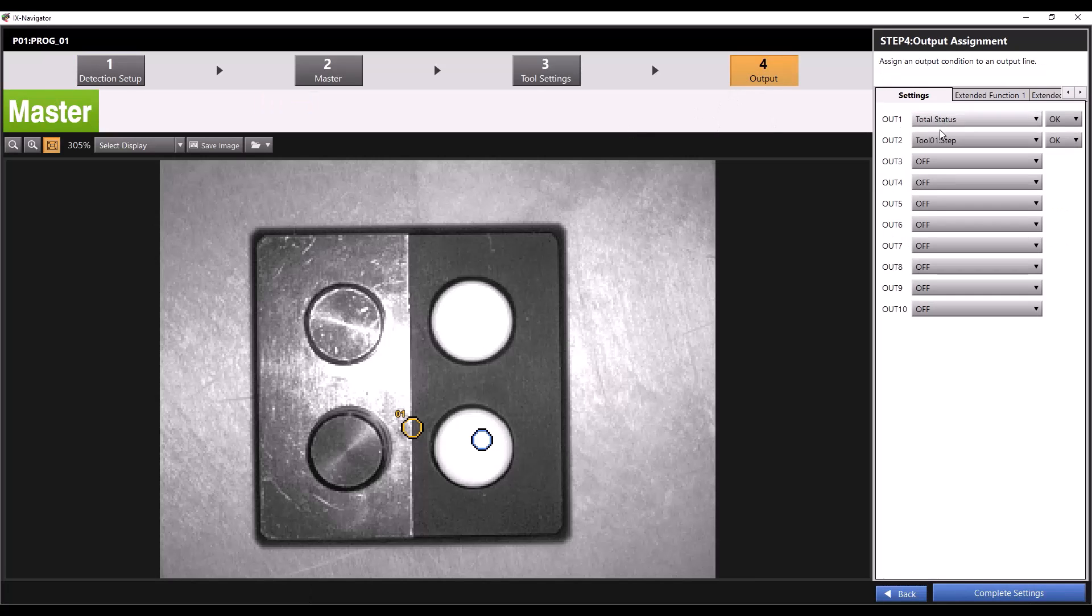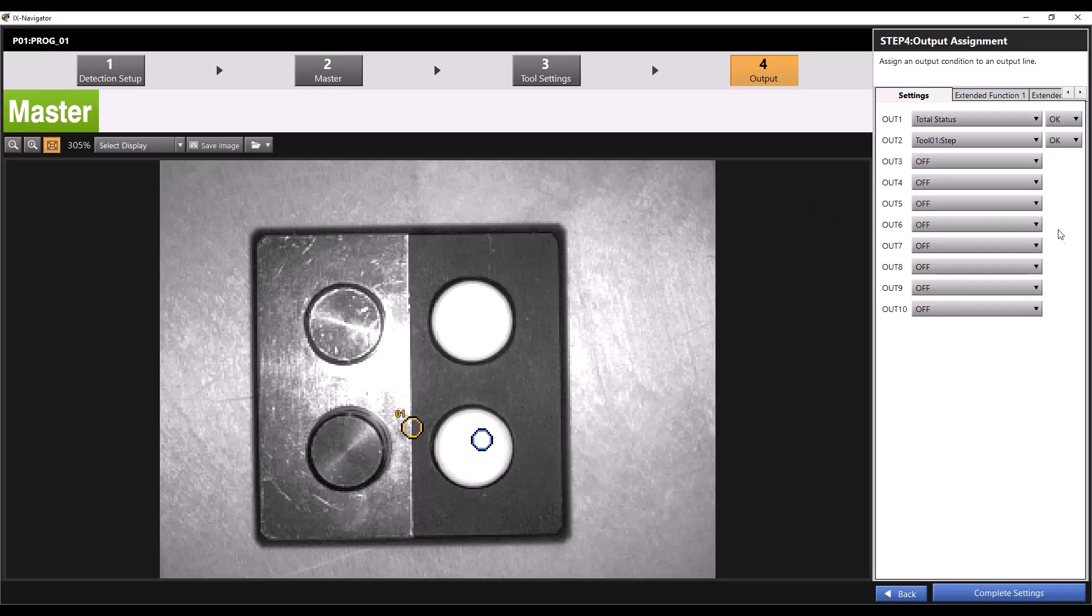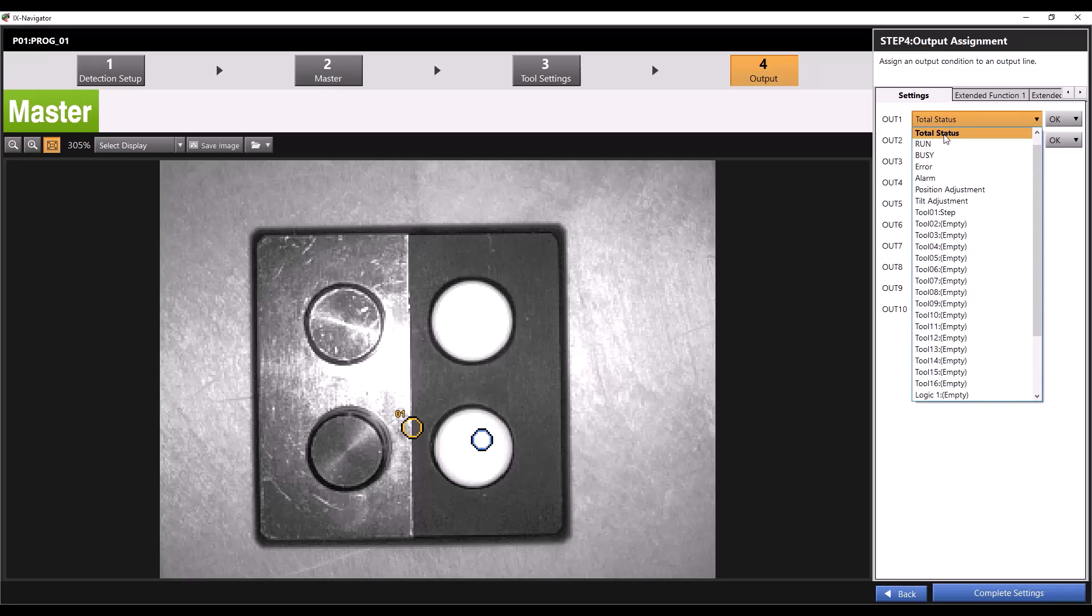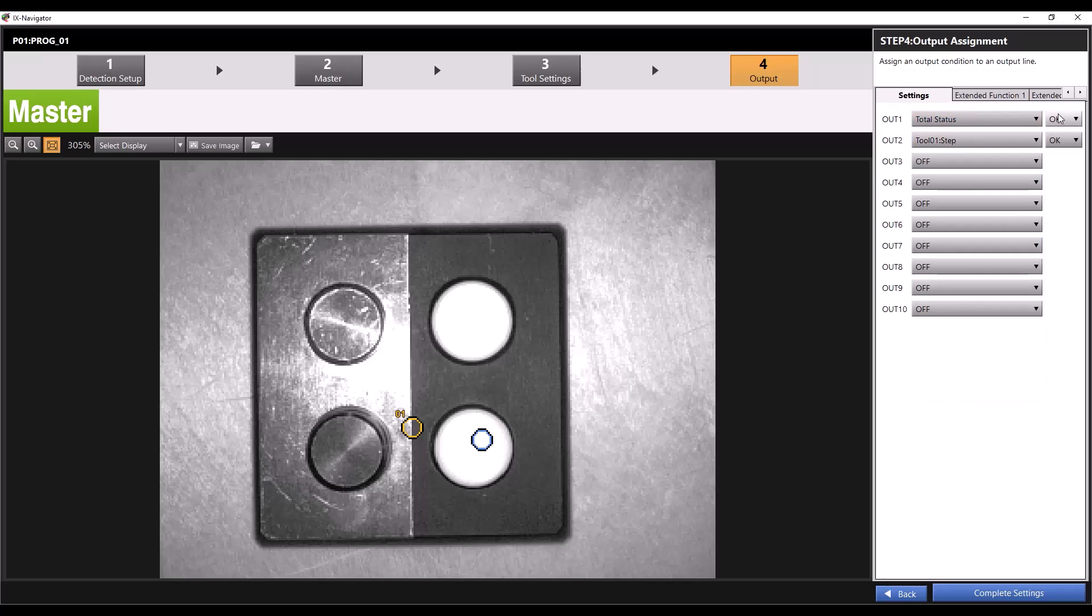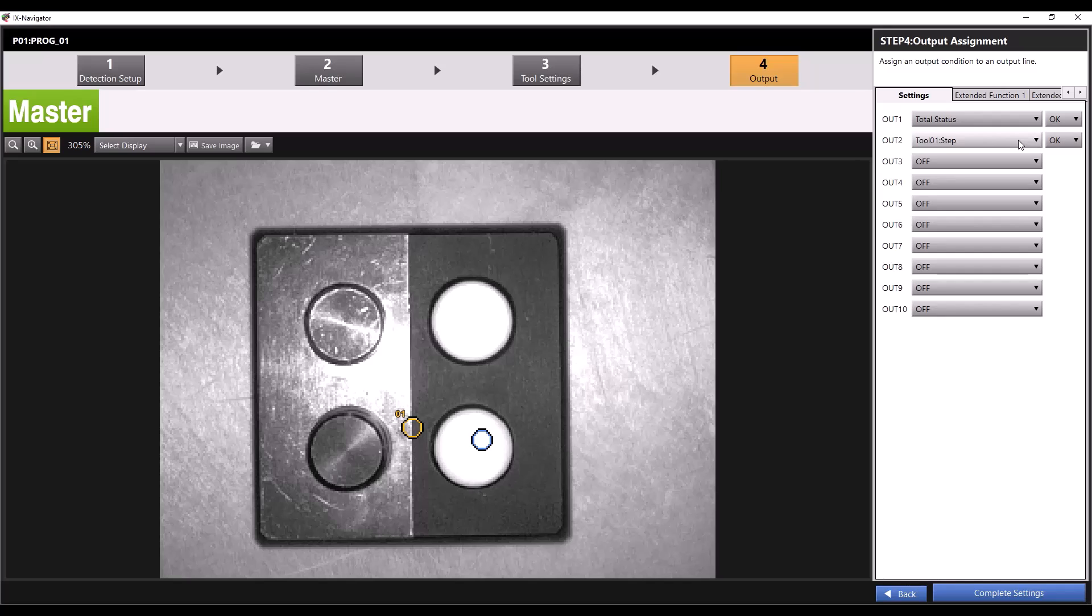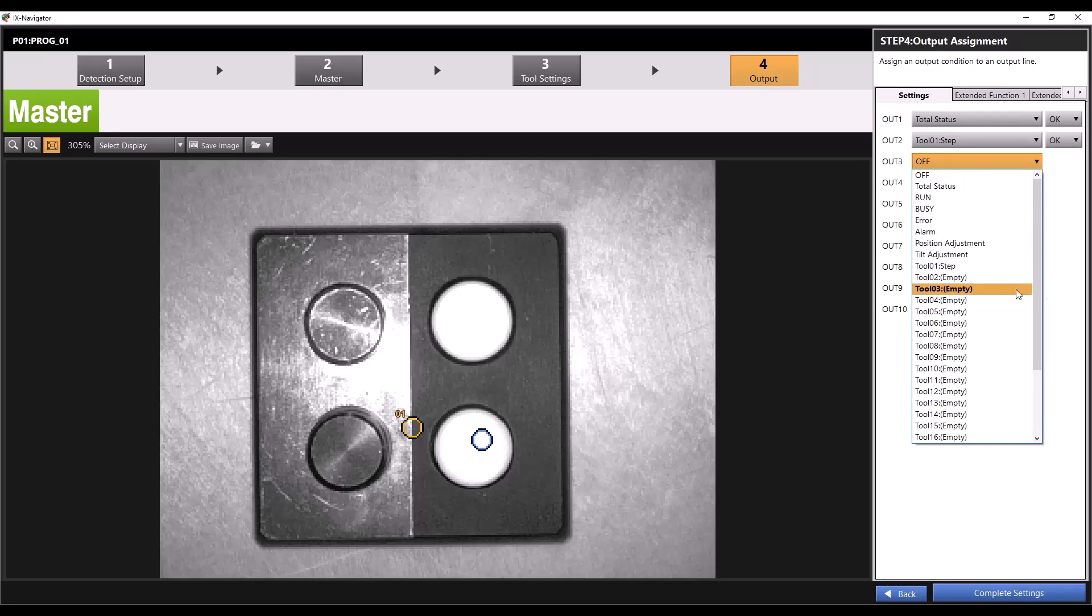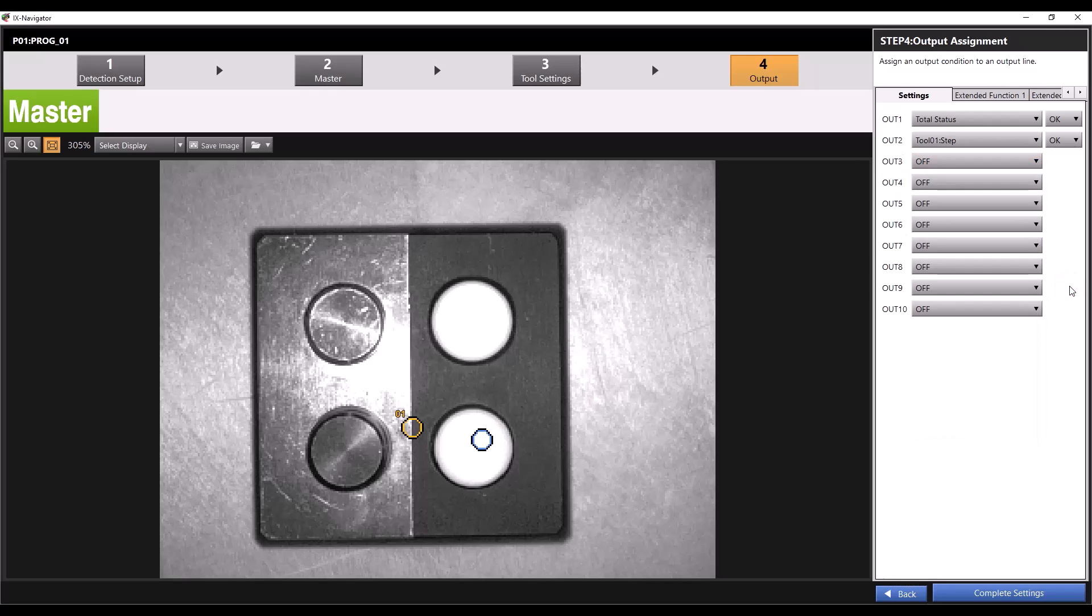Our list of outputs on this screen will correspond to 10 bits in the PLC labeled external output. For example, we'll leave output 1 as total status OK. This will correspond to the bit external output 1 in the PLC, turning that bit on when the IV determines an OK judgment. We can assign output 2 to tool 1 OK, this will correspond to the external output 2 bit in the PLC, turning that bit on when tool 1 gives an OK judgment. This applies to the rest of the outputs you set during this step.